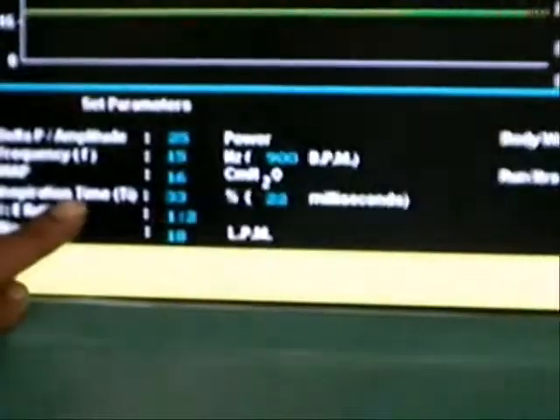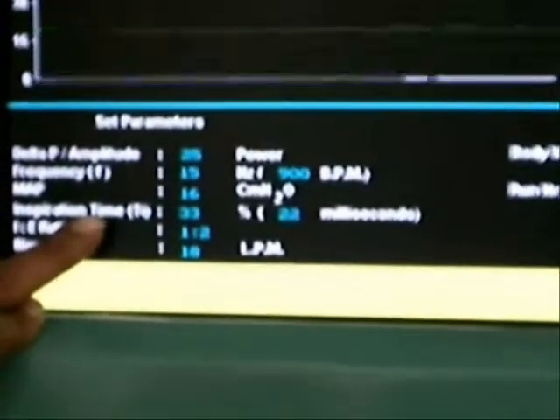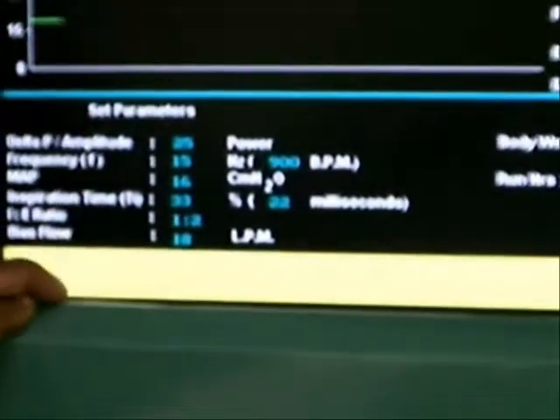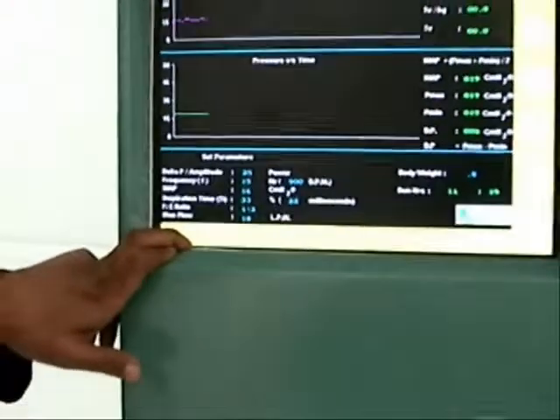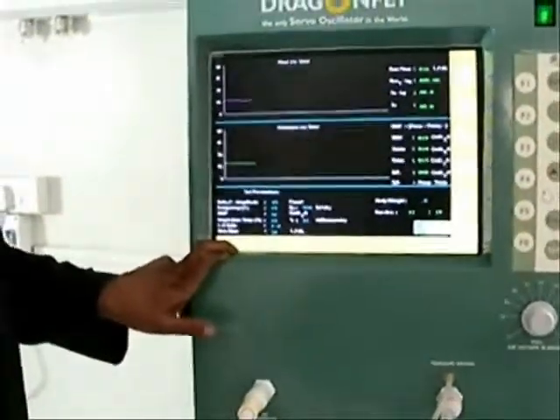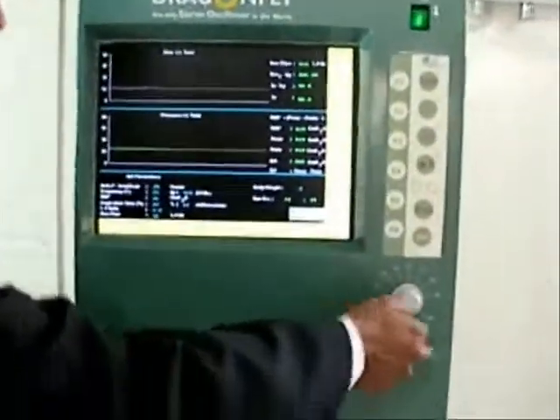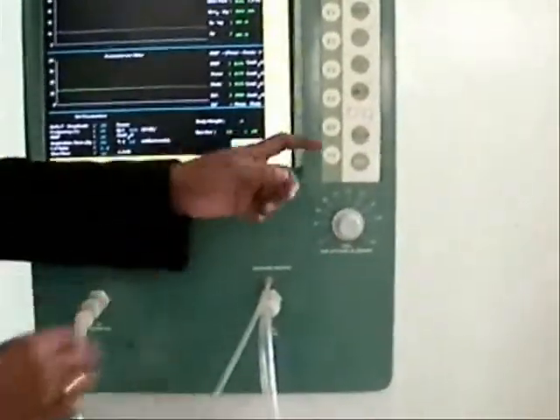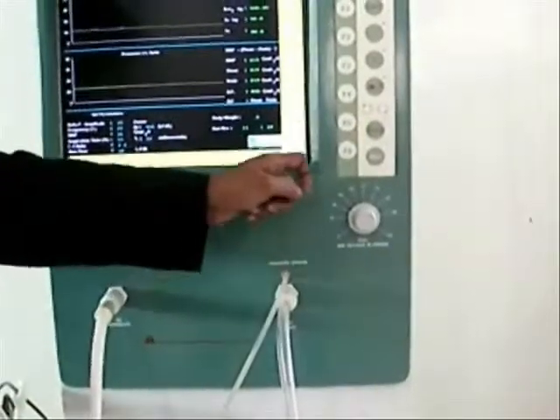Inspiration time, we have talked about, can be set at 33% or 50% of the duty cycle time. Normally the inspiration time is never changed. It's always 33% so that you have an I:E ratio of 1:2. Now all the parameters are set. Here you have an air oxygen blender, so you can adjust whatever FiO2 is required. You can set the FiO2 percentage.